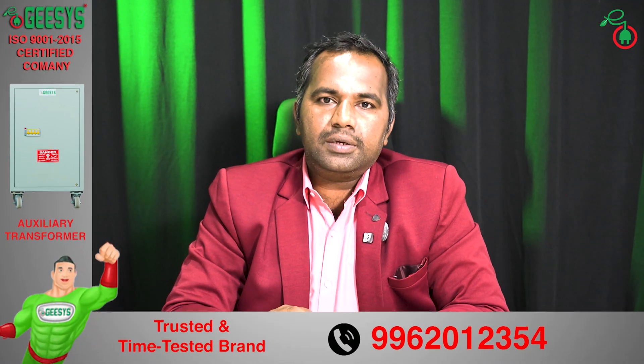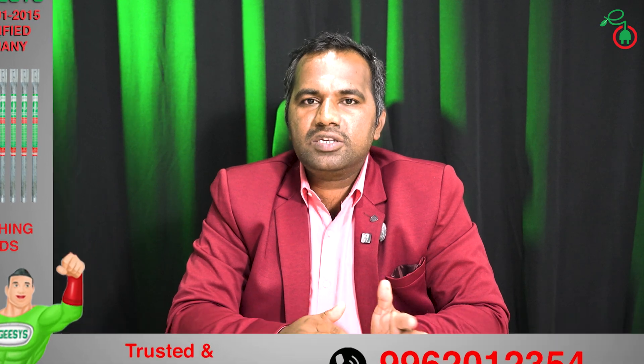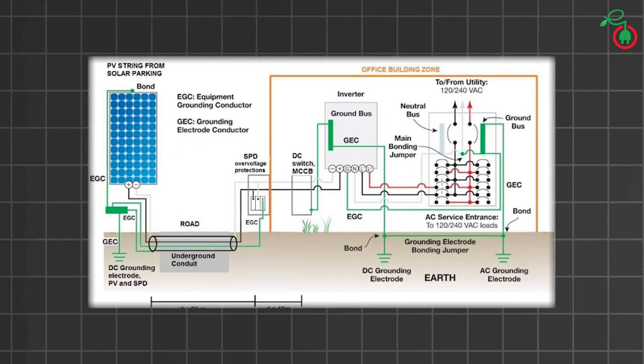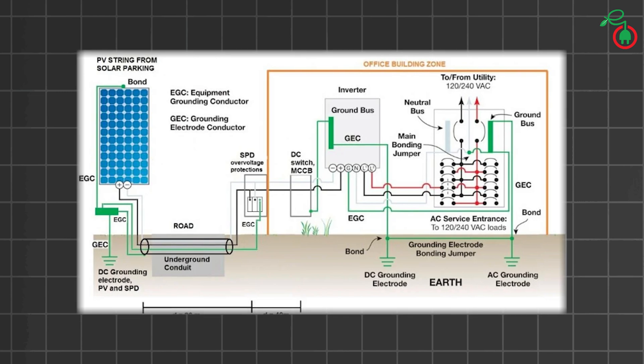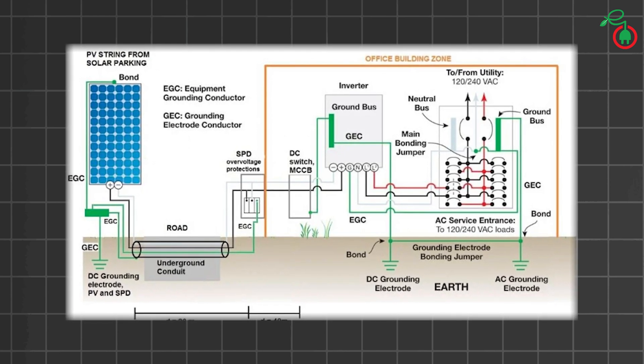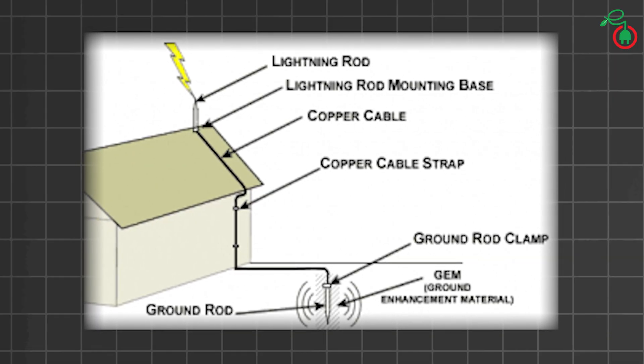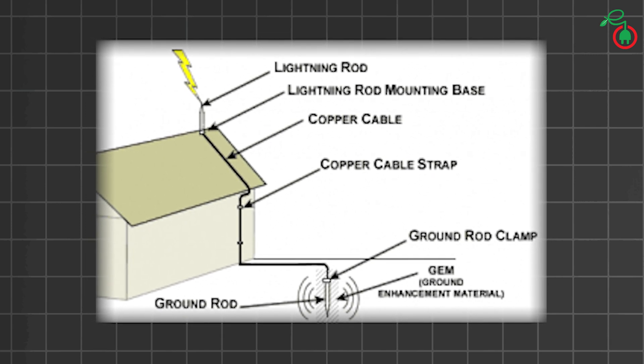The second is SPD earthing. AC DB and DC DB will have a DC SPD and AC SPD, and both have to be earthed separately. In case of AC side surges or DC side surges, the surge will go directly to the earth pit. The third is lightning protection earthing — in case of a lightning strike, the lightning arrester will capture the lightning and pass it to the earth pit.